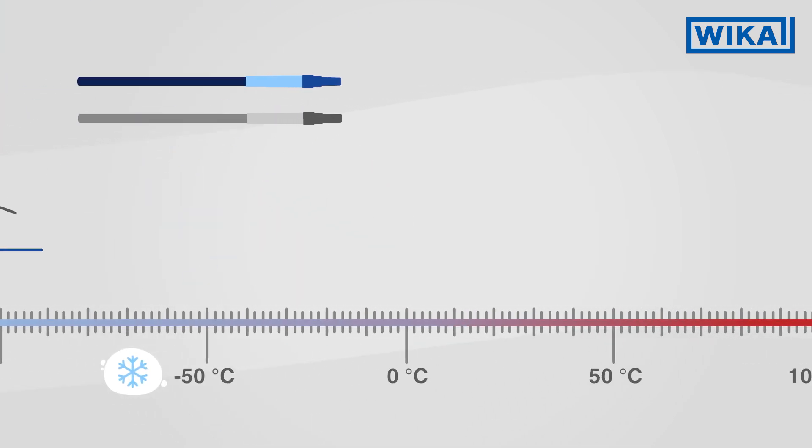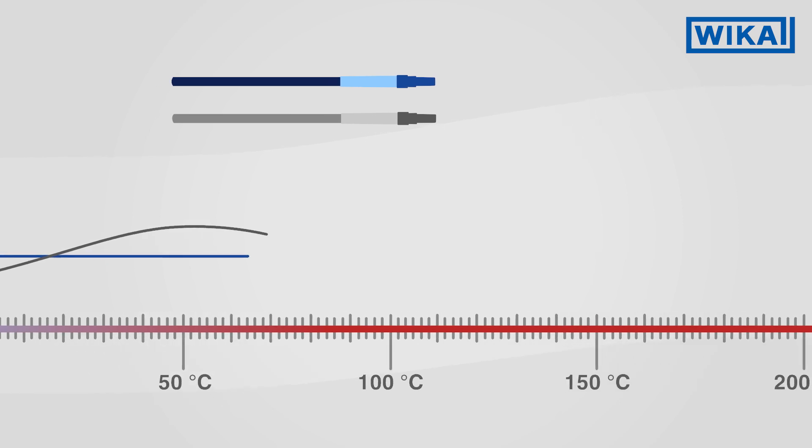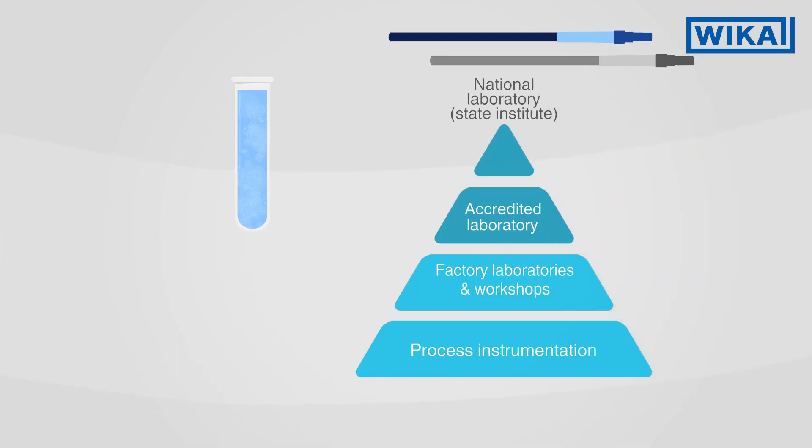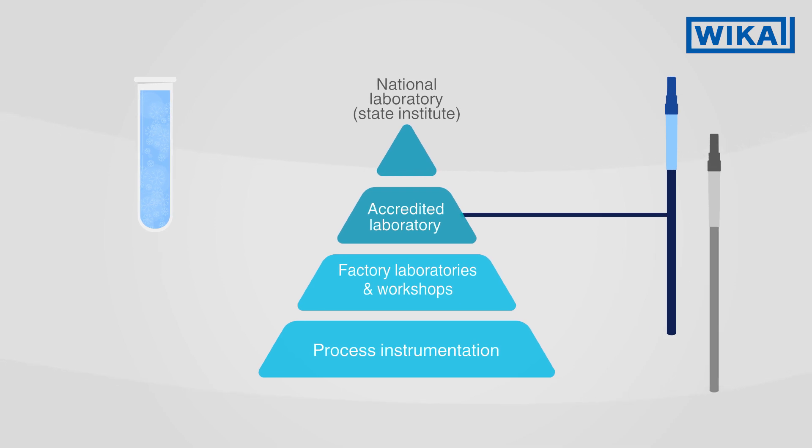At different measuring points, the deviation of the test item from the reference thermometer is determined. The traceability of the reference thermometer enables different levels of accuracy. The measurement uncertainties here are noticeably higher than in fixed point processes.